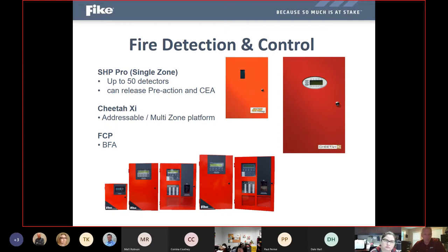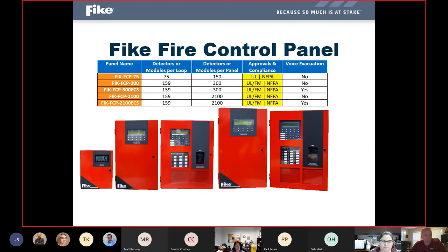We've got our Cheetah XI addressable panel for releasing across multiple zones. And you're talking 250 plus zones that we can program into this to monitor much larger and complex areas and sites and facilities. And then our fire control panel product line at the bottom there, which is for building fire alarm. And those building fire alarm panels are different in size, but capable of addressing just about any size site, any number of buildings. They're very networkable together, so that regardless of what size the facility or site is, we can link together and program in whatever it takes, from just the detection and annunciation, to emergency responder systems, emergency communication systems, mass notification, voice evac. We can do whatever is needed to meet the requirements of any jurisdiction's fire codes from a fire alarm system standpoint.